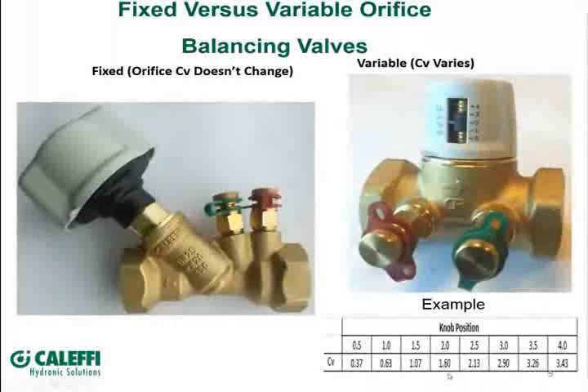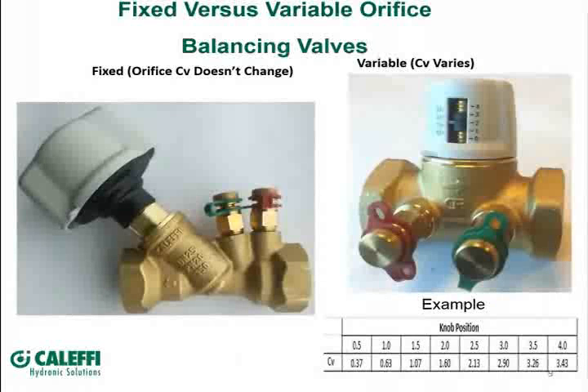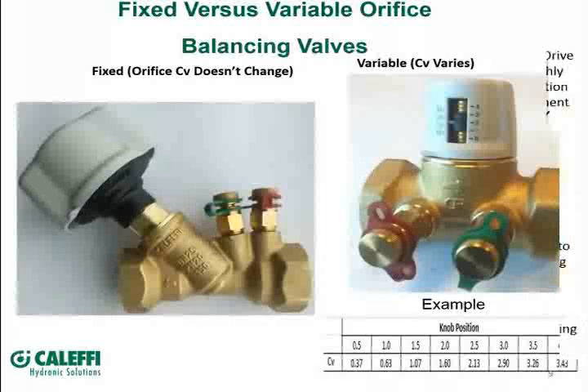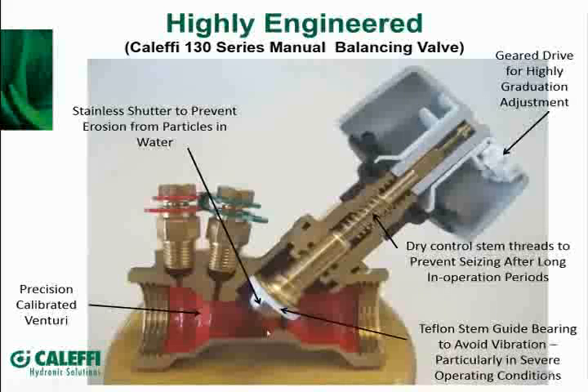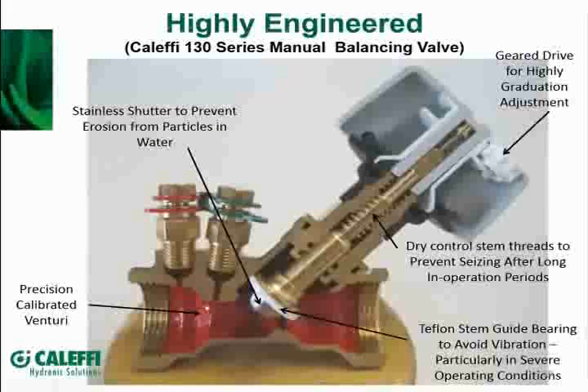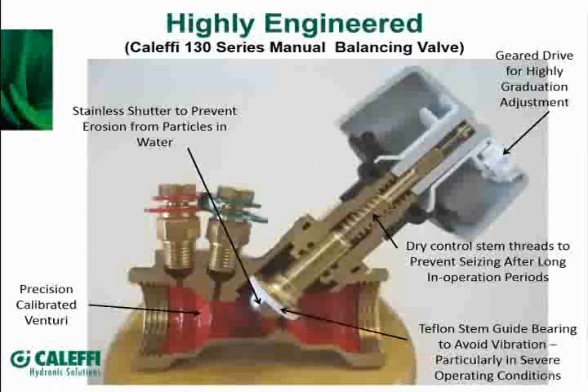There are different ways to balance systems, and these valves would be applied for different applications depending on what kind of adjustability you need. Here's a cutaway of the 130 valve — you can see the venturi orifice. That orifice being fixed between these two test ports is why that relationship doesn't change. Changing the adjustment yes allows you to change flow and balance with this valve, but you can't change the relationship across those two fixed ports, which is why it's considered a fixed orifice balancing valve.